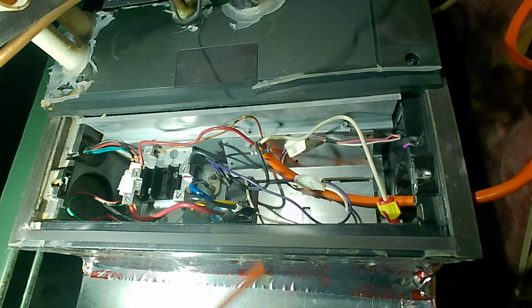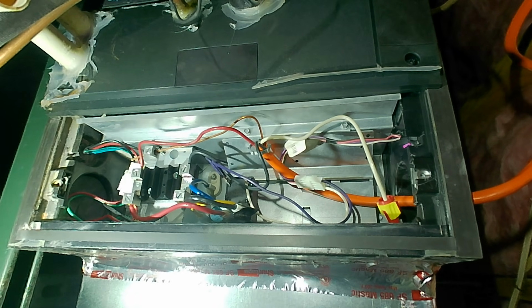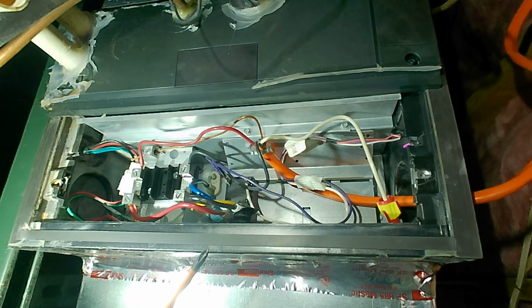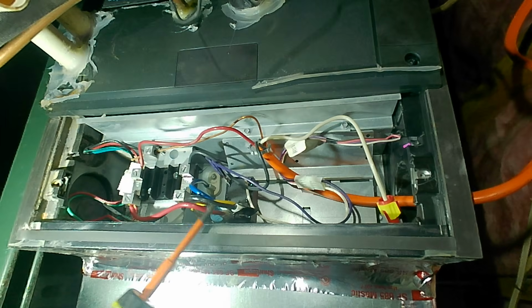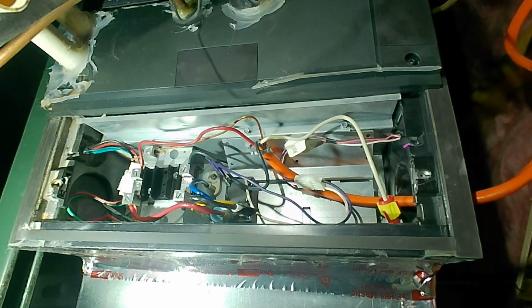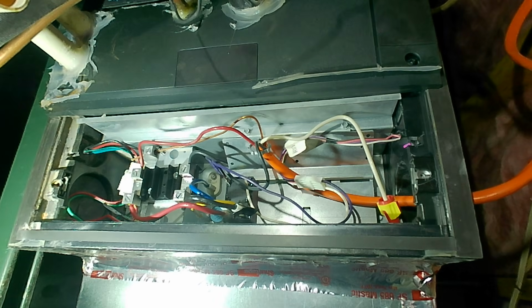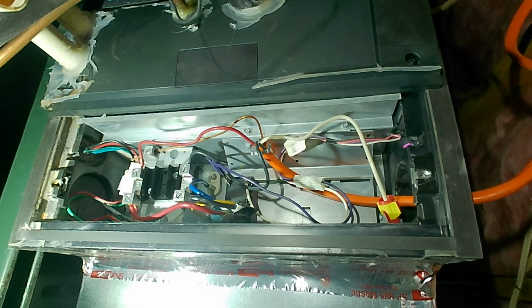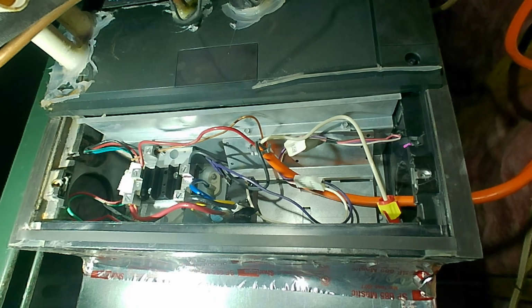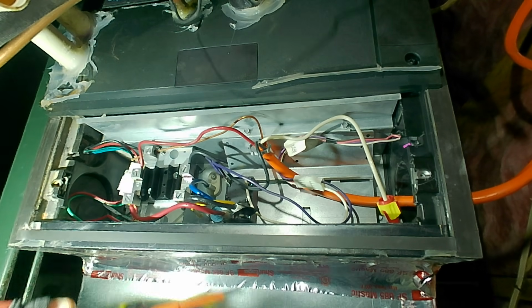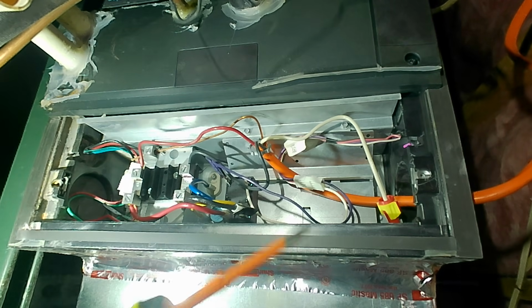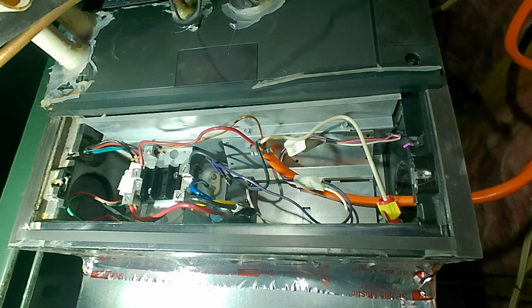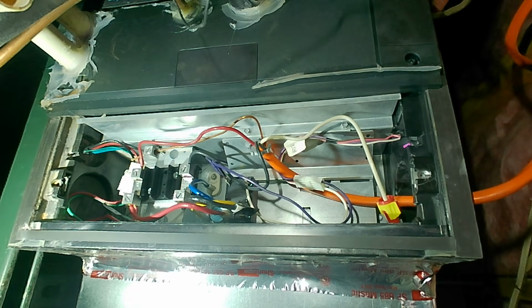and just jumped them out over there in the blower compartment. Got to have the G energized, fan energized on this unit for the relay to close. But after about 10 minutes, I disconnected jumpers on the low voltage, blower shut off, but my relay still had 20 amps on it. Pulled the disconnect out 3 or 4 times, and yep, eventually it would open. So this will be the third set we found now where this relay is sticking in the high voltage limit. So we're just going to do the whole set of heat strips and get that over with.